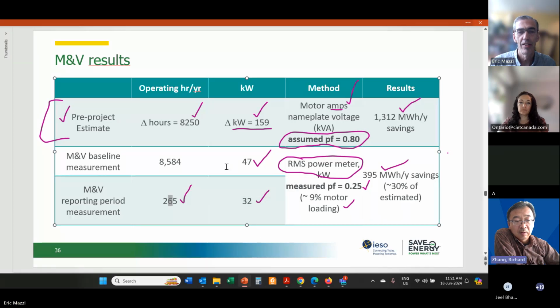Okay, but that's how we did it. And that's pretty common. For those who've maybe done M&V analysis, if you use the reporting period hours and multiply by the difference between baseline power and reporting period power, what that means is you're using operating hours as a routine adjustment in your calculation. If that doesn't make perfect sense, that's fine. That's how it works in the details. That's pretty common in industrial. Thank you. Yeah, good question.